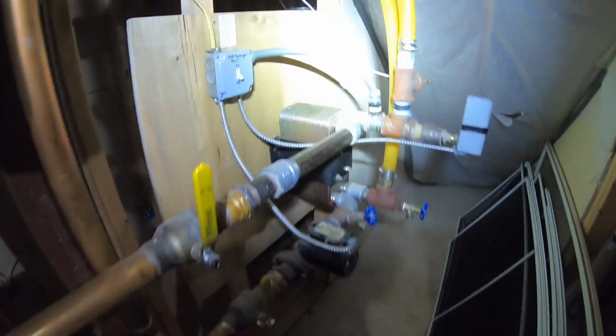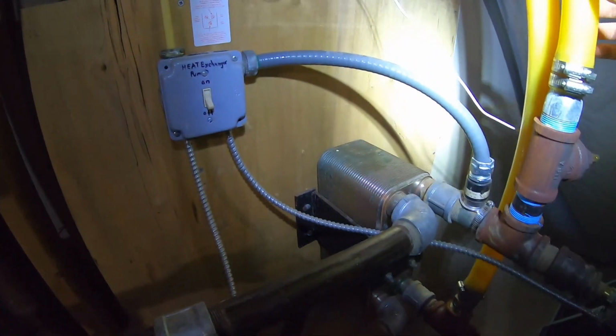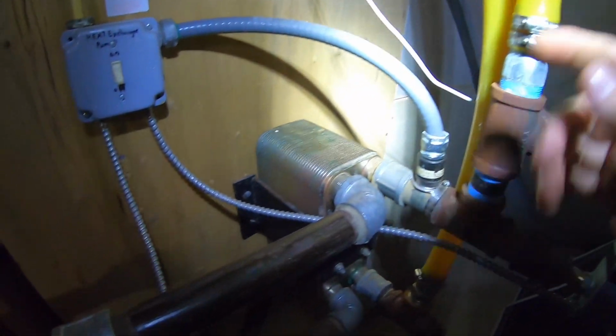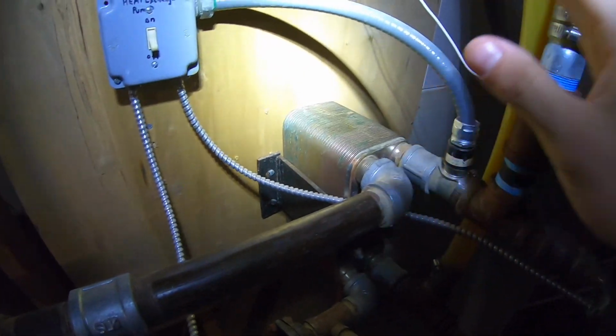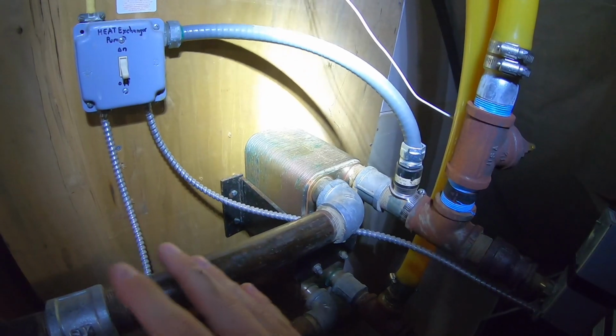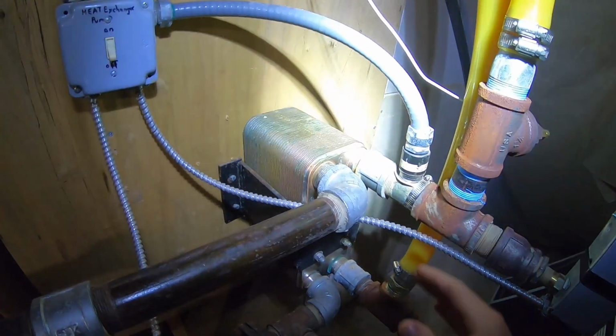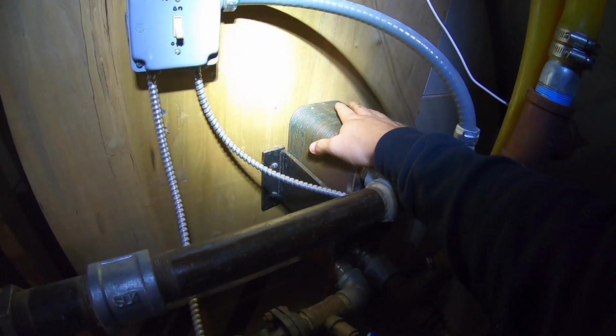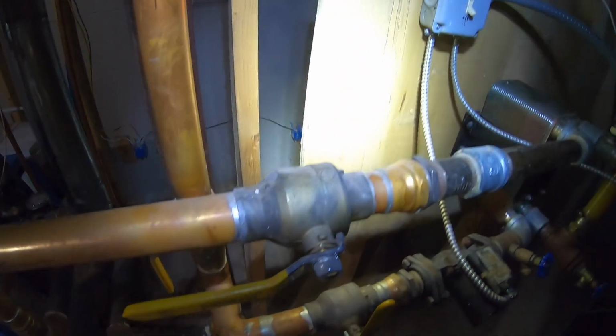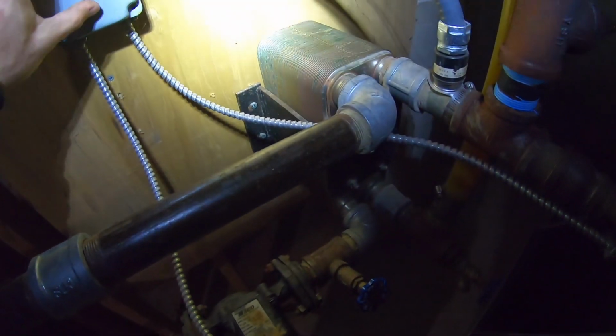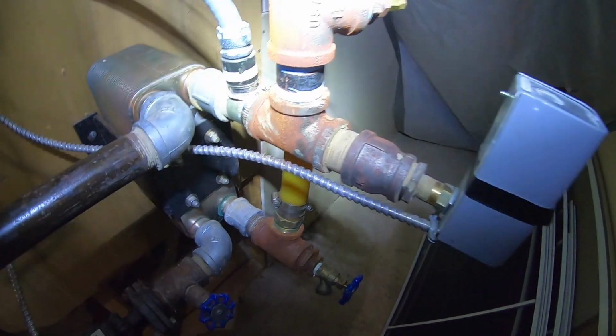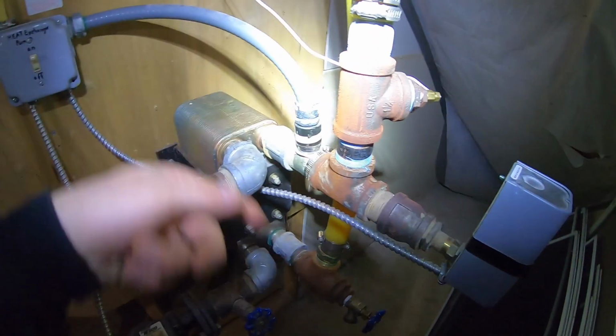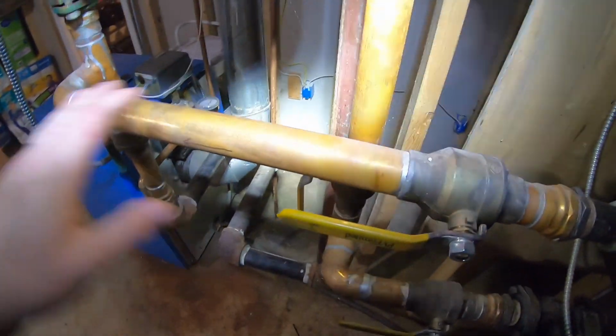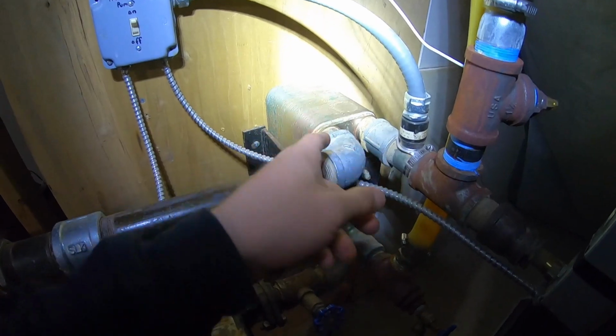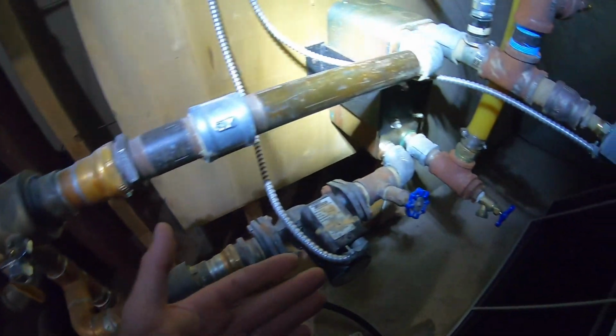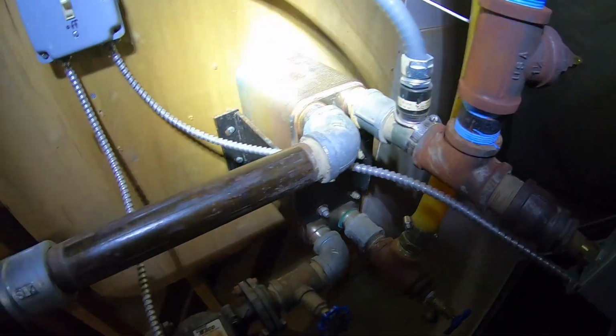This is pretty much how an outdoor boiler works, I'll touch on this more in the next video. This is your supply, and your return runs through a heat exchanger. The water in the outdoor boiler never actually flows through the home like your baseboard or furnace, it flows through a heat exchanger. So we're going to turn on our valves, then turn on our heat exchanger, and go plug our pump in. That's going to start circulating this water, and once 180-degree water circulates through the heat exchanger, our oil won't kick on as long as our wood is nice and hot. Let's go out there and plug it in, and then we should be good to roll.